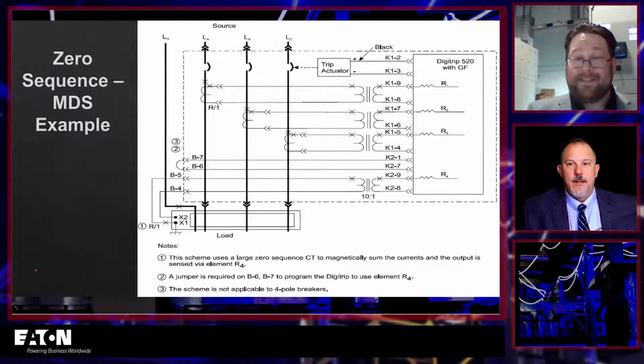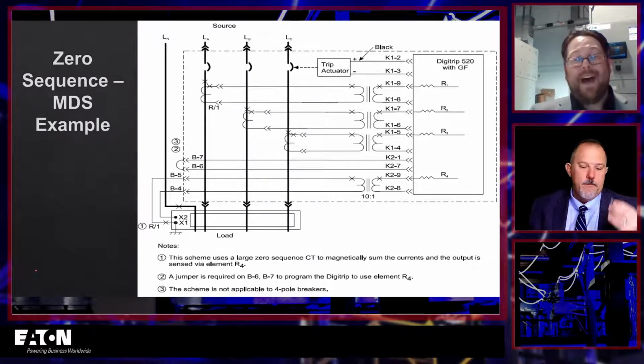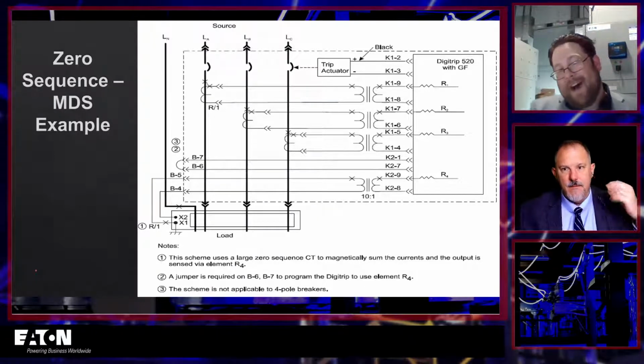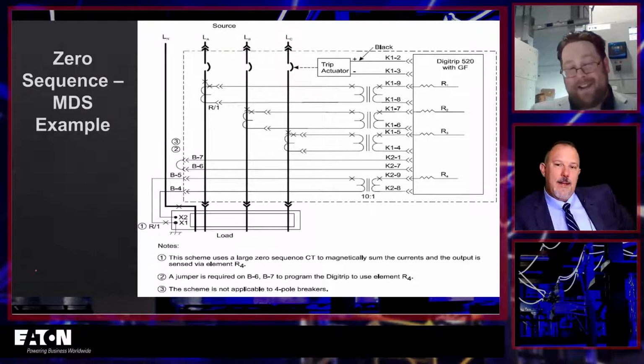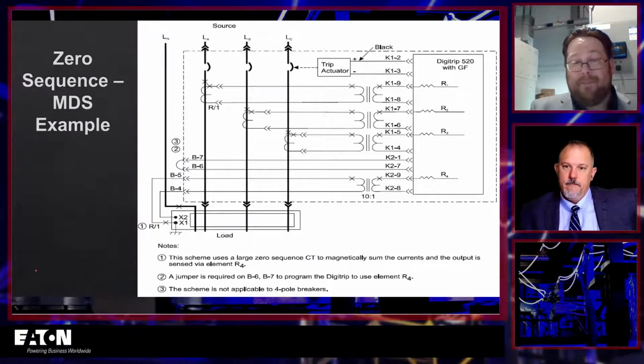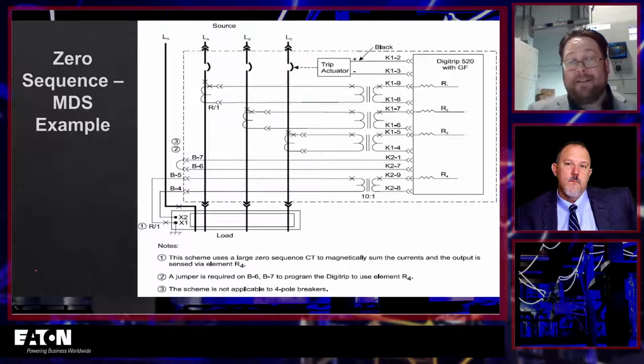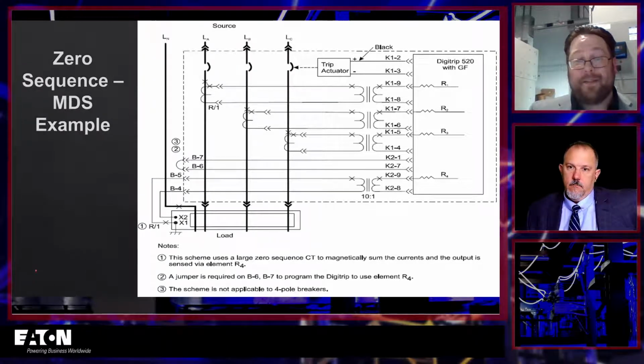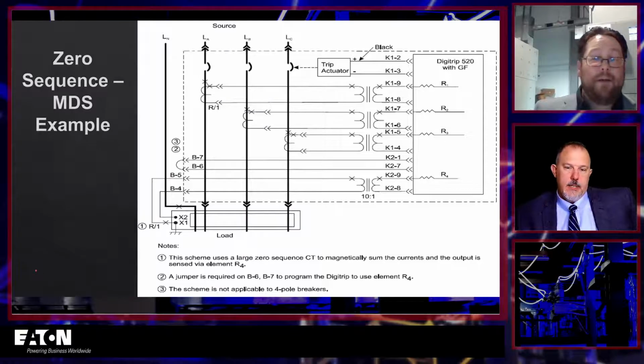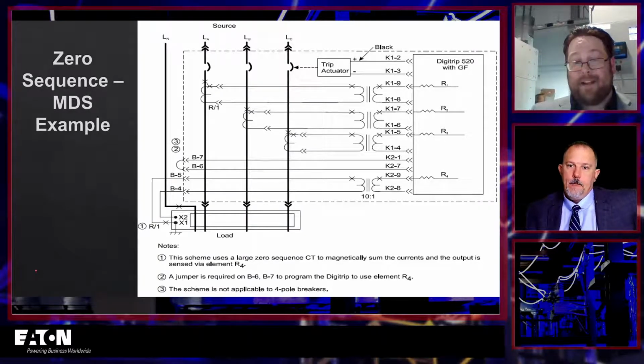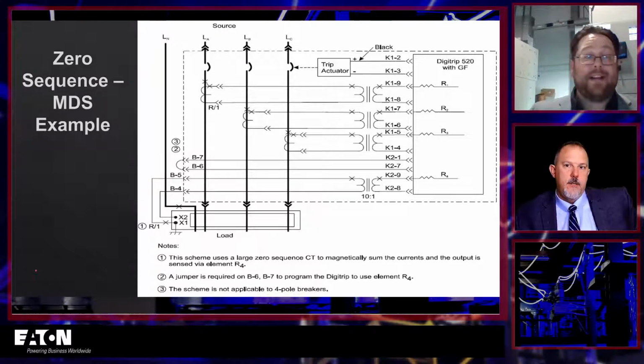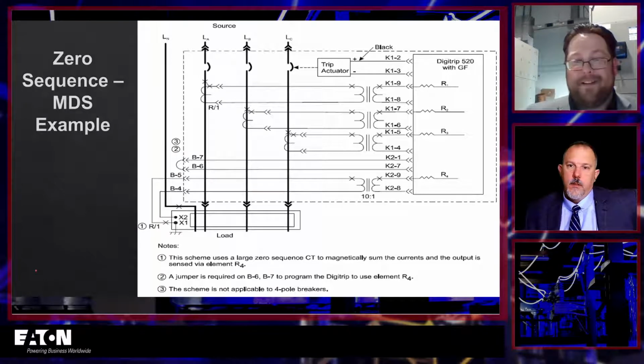It's coming off the phase sensors, right? So now we need to make sure I'm testing a high enough current that I can have my trip guaranteed. But now I need to plan for how do I actually power the trip unit so that I can see all this happening. Maybe I need to have more current injected into the phase to take care of that. Maybe I need to have an auxiliary power supply into my trip unit to make it run and show all the.